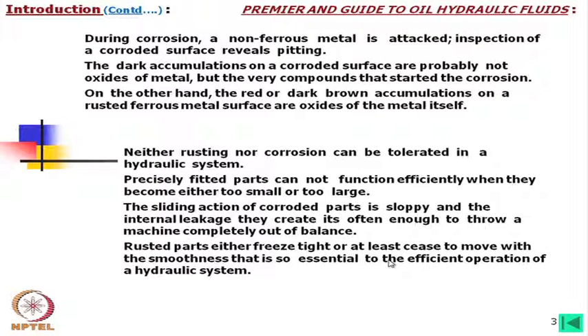Rusted parts either freeze tight or at least cease to move with the smoothness essential to efficient operation of a hydraulic system. Due to rust, a leakage path may be closed, but if there is a moving path, rust will prevent the motion. Furthermore, rust particles mixed with the oil deteriorate its quality both physically and chemically.